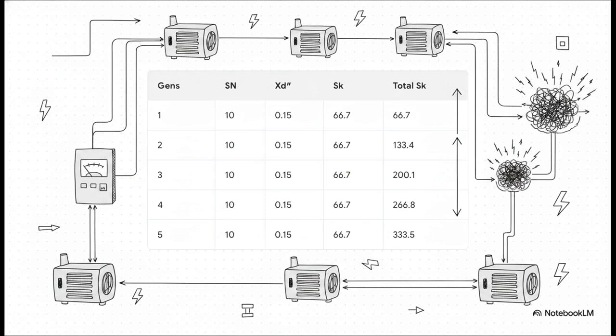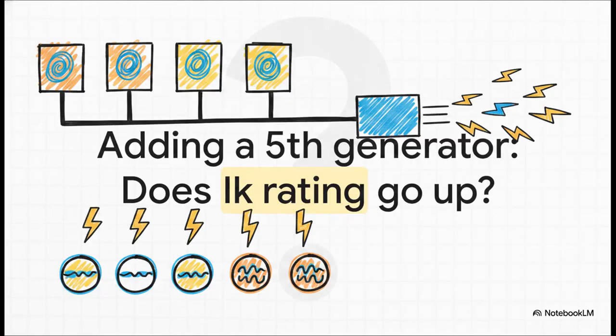Every single time you parallel another machine onto that main switchboard to gain some redundancy or extra power, you are simultaneously raising the total short-circuit violence that the network can produce. All right, I want to throw a scenario directly to you to make sure we're tracking this, because it's a super critical concept. Imagine you're down in the engine room. You've got 4 generators already running on your busbar, but the ship needs more power, so you parallel and add a 5th 10 MVA generator to the board.